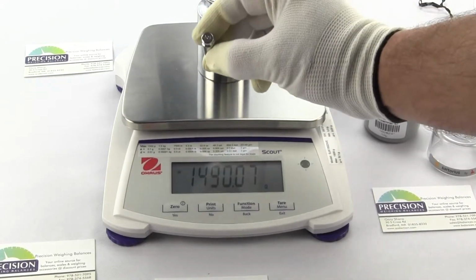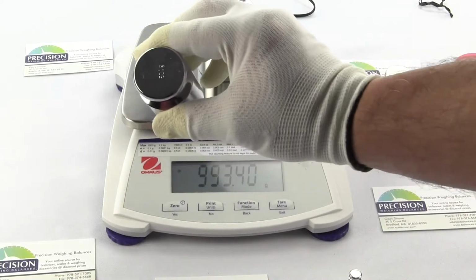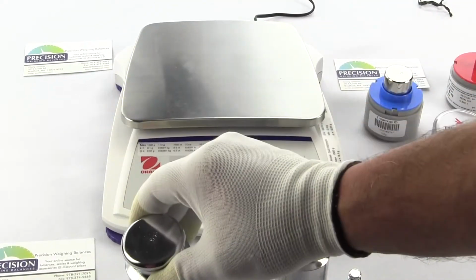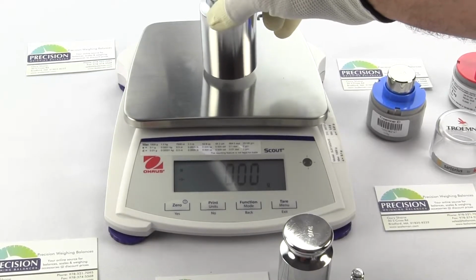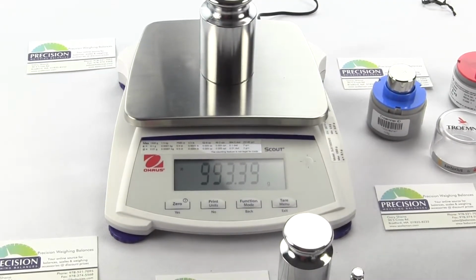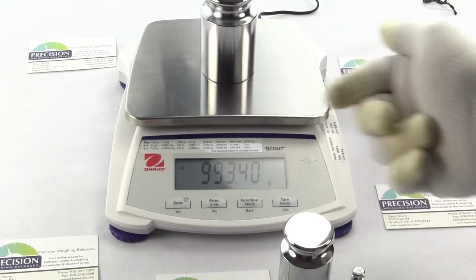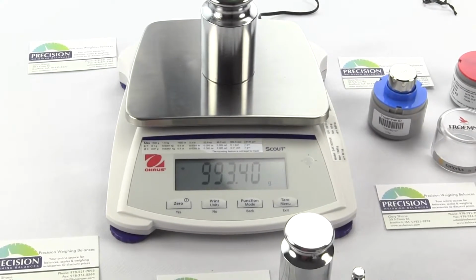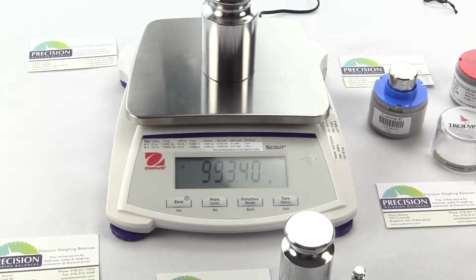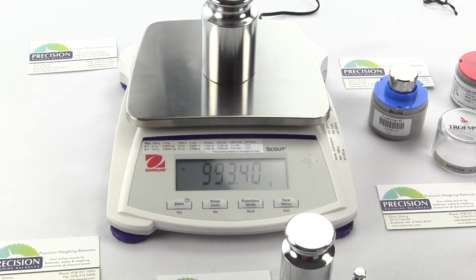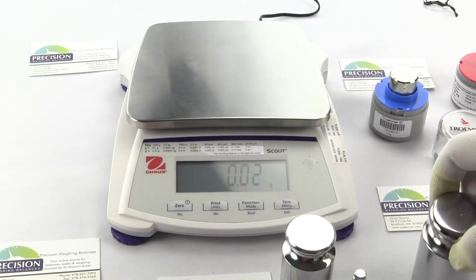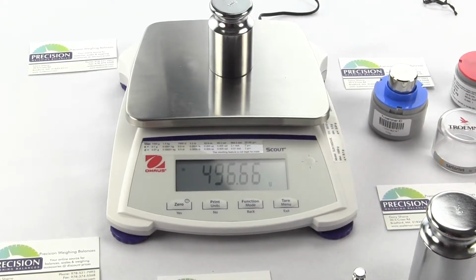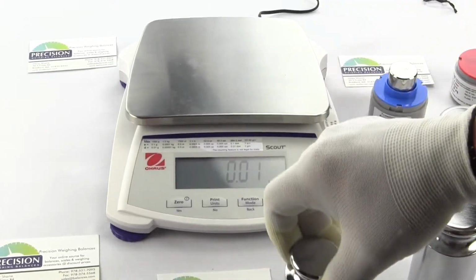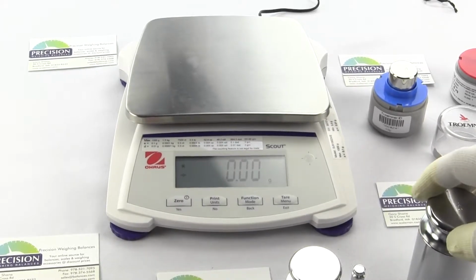If you look here again, this is a 10 gram weight, a 500 gram weight, and a 1 kg weight. So what would happen is, if you were a person that had 1,000 grams of sterling silver and you were going to sell it, a pawn shop owner would say, okay, I'm going to pay you on 993.4 grams. So they would be shortchanging you altogether 6.4 grams. So this is why the scale gets locked out. You can see again, 500 grams, if I miscalibrate it, would show 496. So that's why when the scale's put into service, you're going to calibrate the scale.